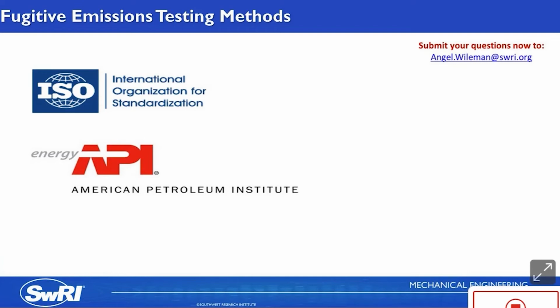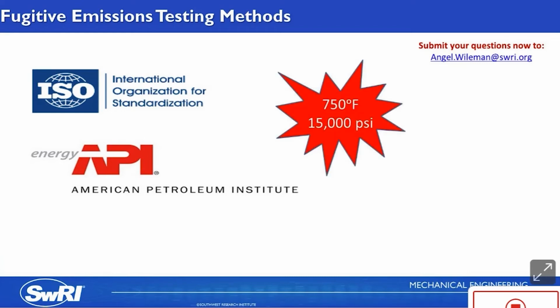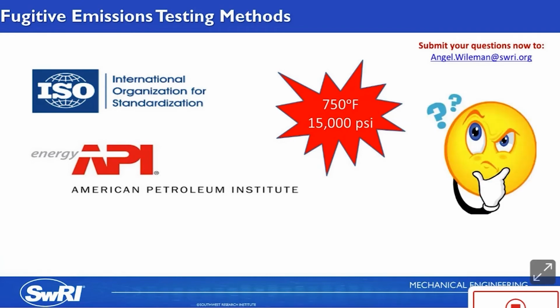The two main focus points for performing fugitive emissions testing, or really any testing, are safety and quality. These procedures involve high temperatures and potentially high pressures depending on the valve pressure rating. We've had test requests up to 15,000 psi at 750 degrees Fahrenheit. So obviously the test procedure poses significant safety hazards, and they must be considered to protect the test operator and avoid equipment damage. Now, quality is a bit more of an abstract concept, but it basically ensures that you've taken the proper steps to acquire accurate data.